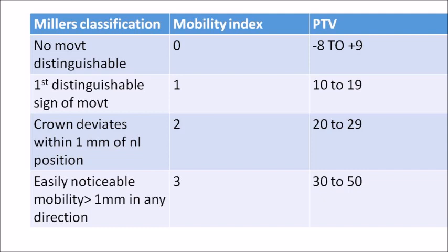Miller's mobility index 1 — first distinguishable sign of movement — corresponds to a Periotest value of 10 to 19. Index 2 — crown deviates within 1 mm of the normal position — corresponds to values of 20 to 29. Index 3 — easily noticeable mobility of more than 1 mm in any direction — corresponds to a score of 30 to 50. So Periotest values range from −8 to +50.